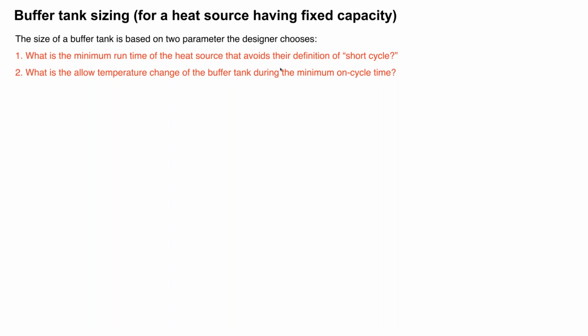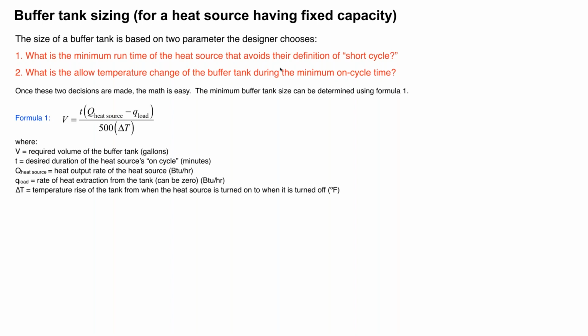If we're turning on a compressor in the case of a heat pump, or a burner in the case of a boiler, we would like to see that run for a minimum of 10 minutes, just so we aren't accumulating literally tens of thousands of on-off cycles over the course of the heating season. The other thing we have to look at is how much of a temperature change the buffer tank will undergo while that heat source is on. The smaller the temperature change, the bigger the buffer tank has got to be. So you can put this together mathematically. It's actually a pretty simple calculation. If we want to calculate the minimum volume of a buffer tank, V, all right?